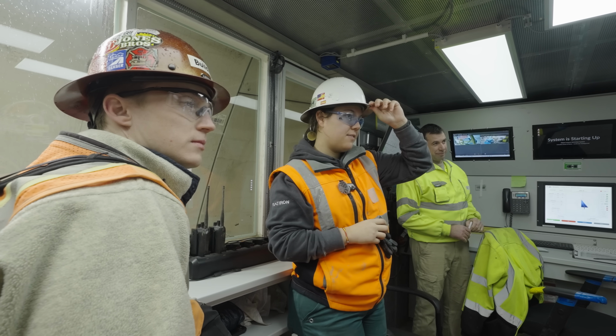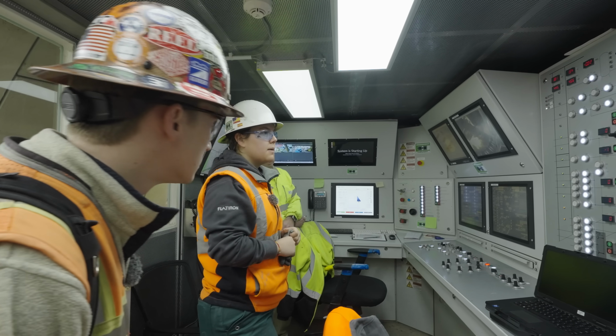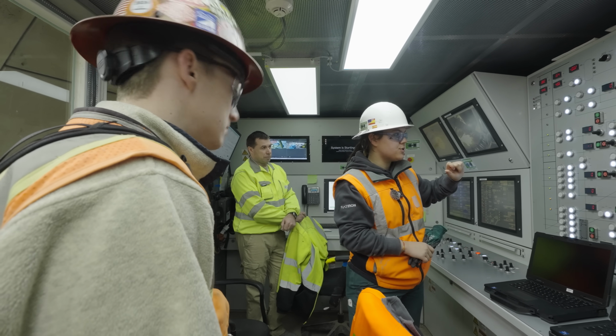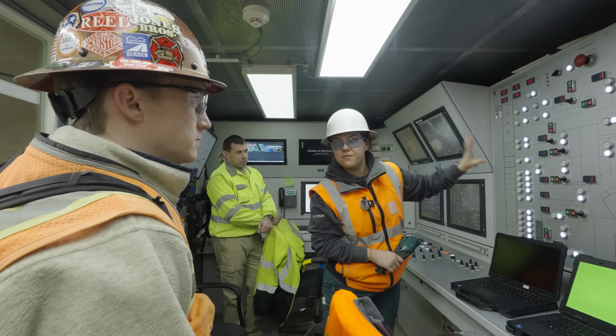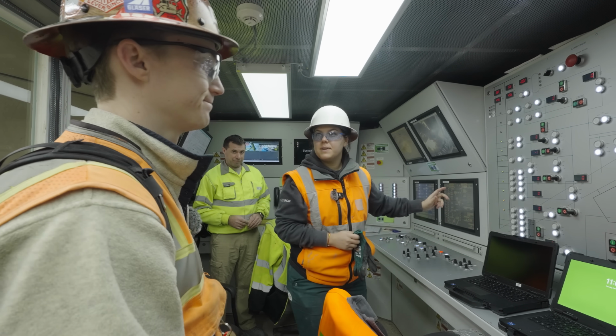This is the schematic of the machine with the different valves. He's able to manually open or manually close whatever he needs to, depending on the type of flow that we need. We are at 3,000 cubic meters per hour normally. Whenever you have any sensors or any pumps that have a flow meter on them, the important ones at least are for the feed pumps for the slurry: P0 means feed pump within the machine, P1 means feed pump to the machine, and P2 means return line to the STP, or feed to the STP. It's a little more complicated than a steering wheel. Think of a Formula One steering wheel.